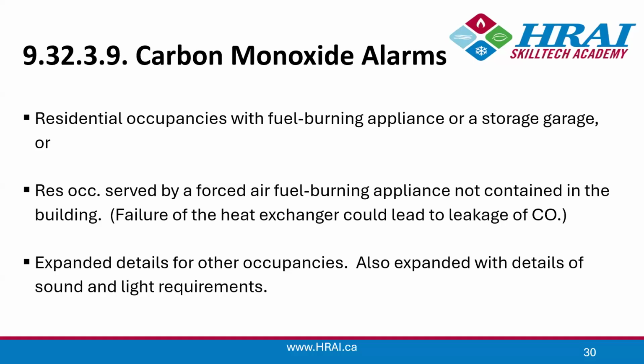In other words, if it's some kind of secondary suite that maybe has a forced air system in a mechanical room that serves both suites, so it's not actually in the suite, it would still require a CO alarm because failure of the heat exchanger could lead to the leakage of CO into the space. And then there are some expanded details for other occupancies.